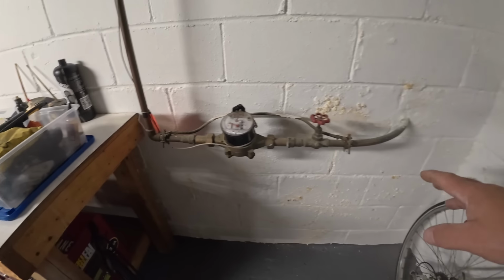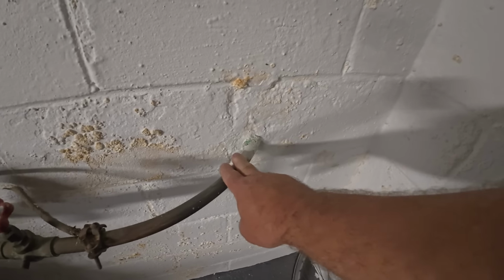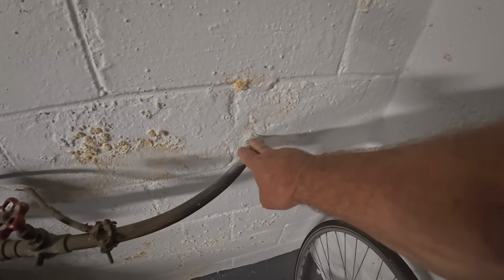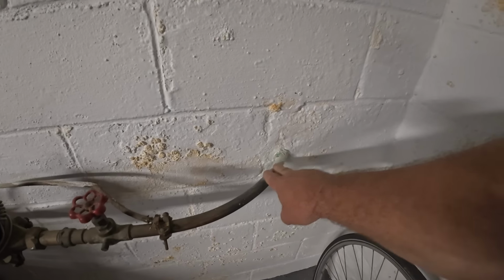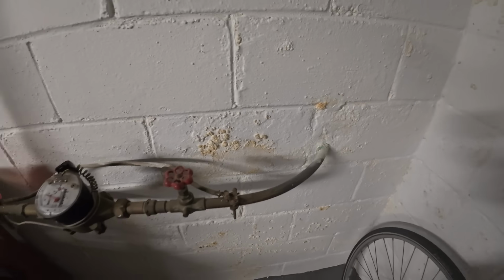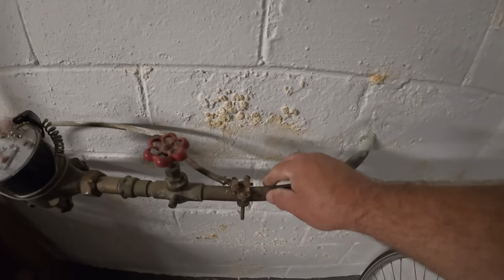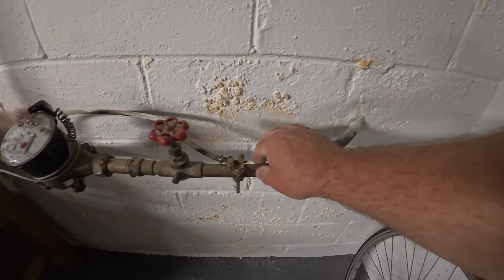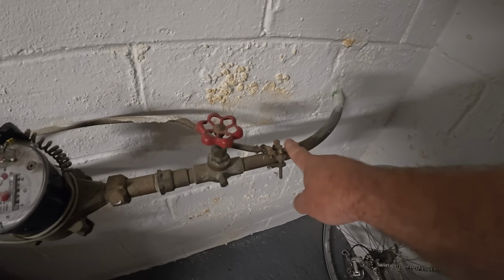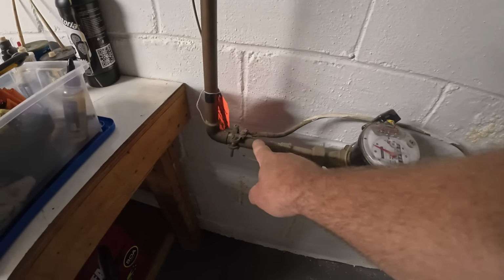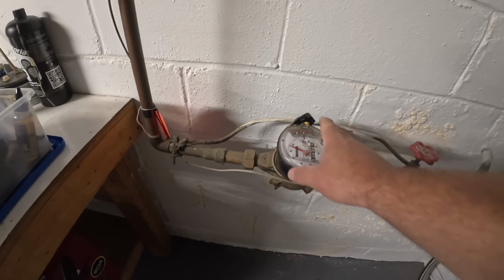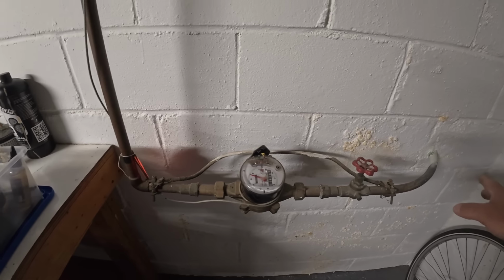This is the main water pipe. This copper pipe goes in the ground for more than 10 feet. We're assuming it hasn't been changed or upgraded. We're going to use some emery cloth to clean up this copper water pipe to get a nice clamp. We're going to do it from the supply side to the customer side, the jumper, in case they ever take this meter out. We still have our grounding electrode connection.